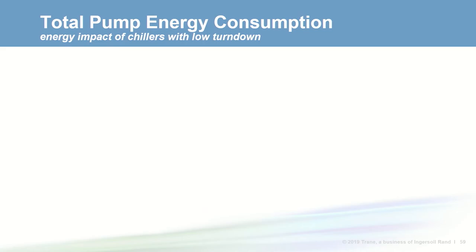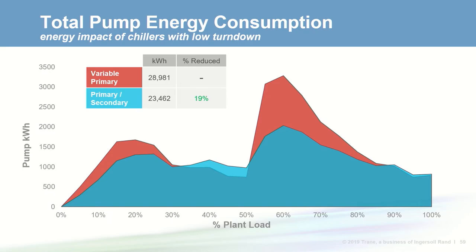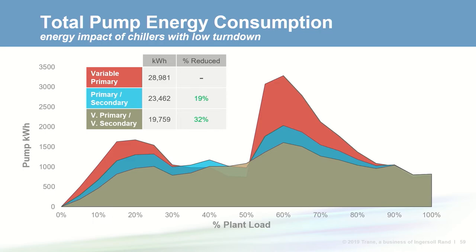We analyzed a load profile from Pacific Northwest National Labs for an office building in St. Louis to develop an annual pump KWH comparison. The variable primary flow system consumed almost 29,000 KWH. Primary secondary consumed 19% less pump energy over the course of the year. The variable primary variable secondary configuration consumed the least at about 20,000 KWH — 32% less pump energy than the variable primary flow configuration.